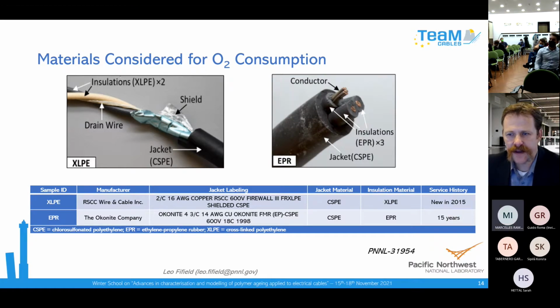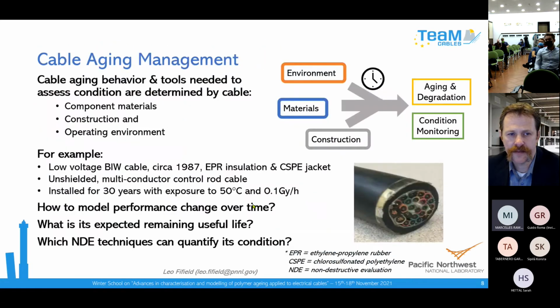Yeah, thank you. Like I said, it's hard to do 40-year experiments on cables, but what we have now that they didn't have at the beginning of nuclear activity is operating experience - plants that have been operating for decades. So harvested material is one way to get actual samples exposed over that time. In this case, the XLPE we looked at was new - we purchased it a few years ago. The EPR was harvested, and the 15 years corresponds to how long it was installed, not how long since it was manufactured. It was actually installed at Crystal River 3 for that long.